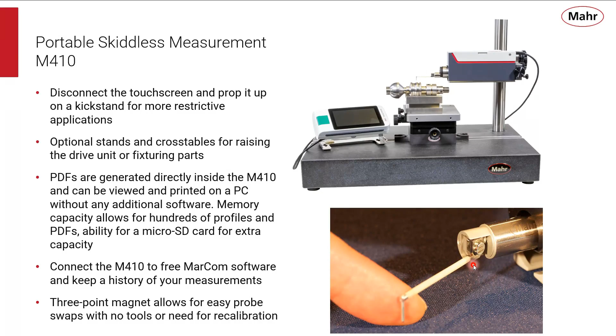So some nice features that will allow for the easiest and most reliable results include automatic probe zeroing, arc elimination when measuring on a radius, and automatic cutoff selection. You can evaluate all parameters on a single measurement, not just RA or RZ. If you need more parameters, you can evaluate as many as you want on a single measurement. The probe system has a 7.6 nanometer resolution and up to a 1.5 millimeter measuring range. You can also use a barcode scanner to automatically begin measurement programs related to certain parts that will confirm you're using the proper programs, proper parameters, and everything is already predefined.